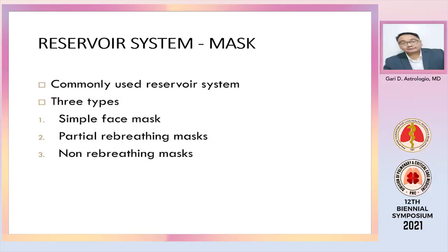For a regular face mask, no, this serves as a reservoir for at least 100 to 200 ml. It's a variable performance device, and your FiO2 varies. It depends on the amount of O2 delivered, the mask volume. So it's quite important for you to give a proper size of face mask, the extent of air leakage because of the inhalation and exhalation port, no, and the patient's breathing pattern. With this regular face mask, you would be able to deliver an FiO2 at around 40 to 60% effectively.